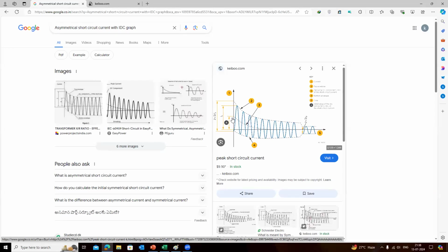Right. Now, next, one more point: the steady state value we are discussing here is a theoretical value, which means it will never happen in the system in practice. Because whenever there is a fault, your protection system isolates the fault in the transient region itself, not in the steady state. If you allow the fault current to reach a steady state, much before that your equipment would have already been damaged, right?